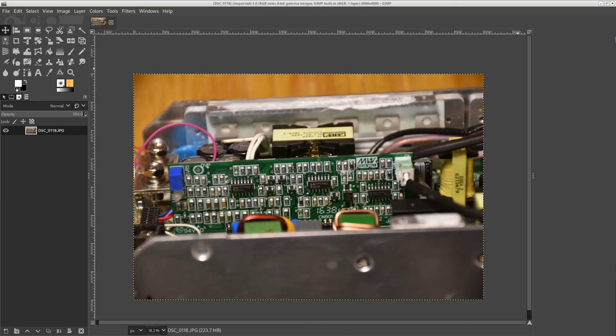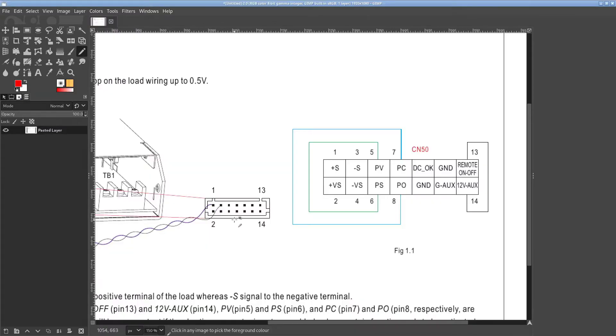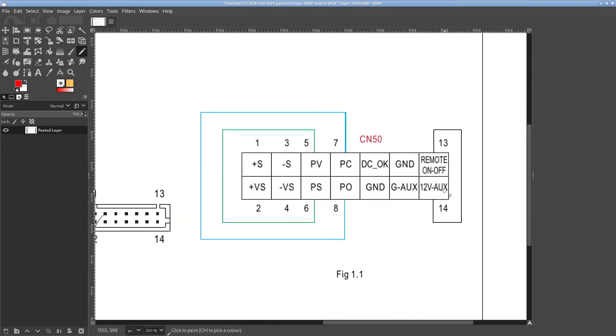I first looked at the unit that I thought was almost working, the one with the solid red LED. I looked at the 12 volt, the auxiliary 12 volt supply that powers the remote on off and a bunch of other stuff.